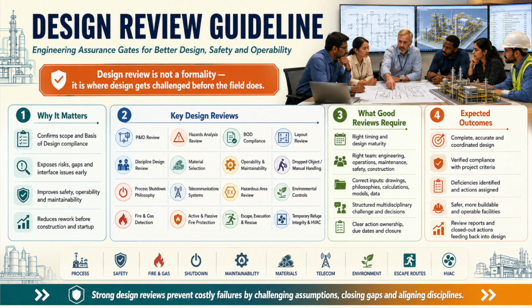Discipline design reviews go deeper. For process engineering, you confirm that process flow diagrams are finalized, P&IDs are approved, hazard review actions are resolved, and flow rates, pressures, temperatures, densities, compositions, throughput, tankage, vessel elevations, utility demand, mass and energy balances, controls, emissions, vacuum conditions, and low temperature cases are properly defined. For piping, you confirm plot plan maturity, upstream data availability, design review action closure, code compliance, line conditions, seismic loads, wind, blast, snow, design life, testing, inspection, vibration, dynamic loads, standardization, constructability, and compatibility with existing facilities.